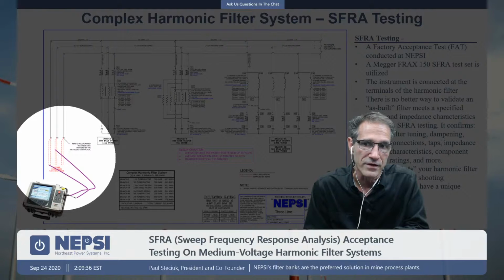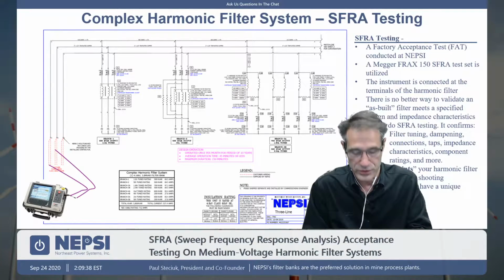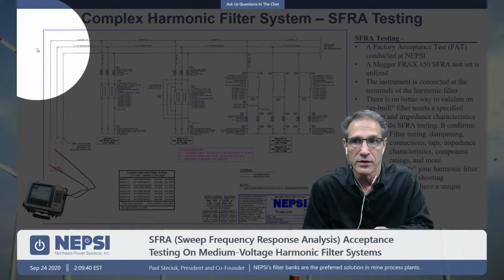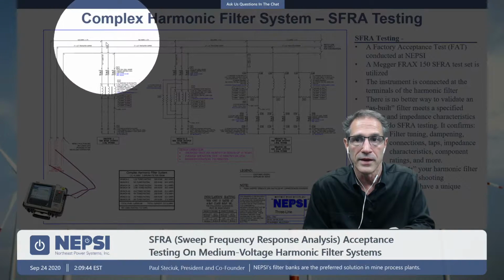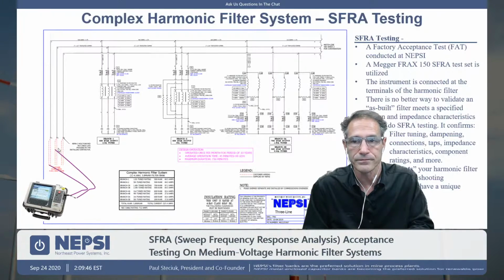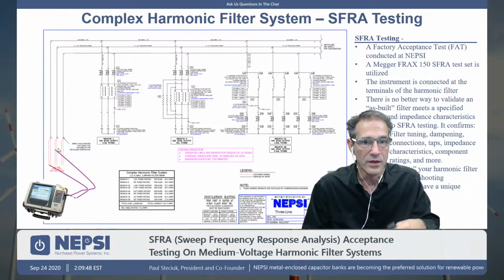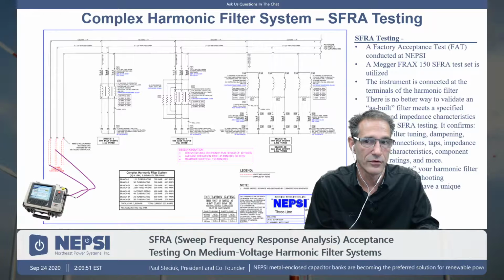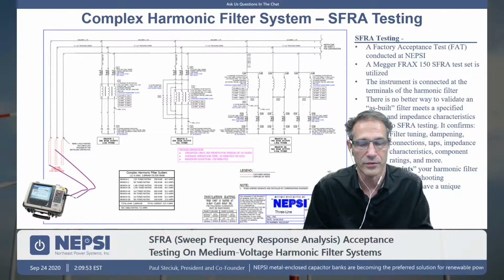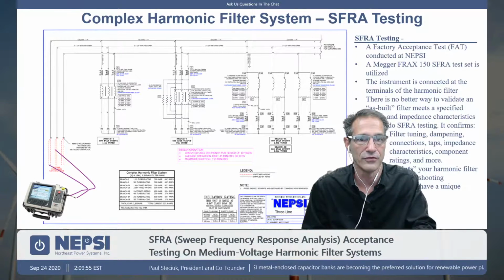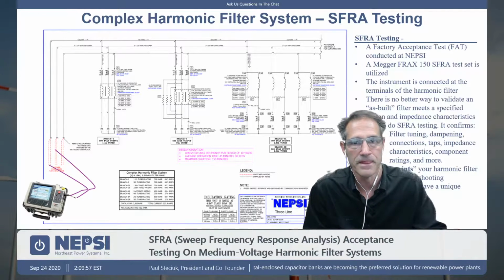Typically, we're connecting phase to phase here, and we're measuring basically the impedance profile through one phase, if you can think about this, through the neutral, back to the other phase. So we're capturing an out and back path, which means that the impedance value we're reading is double what we would actually see line to neutral. It's a line to line impedance value.